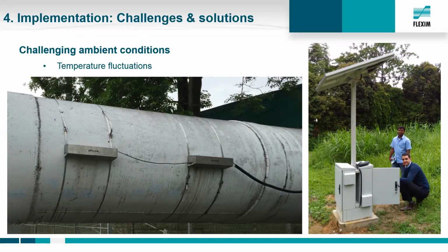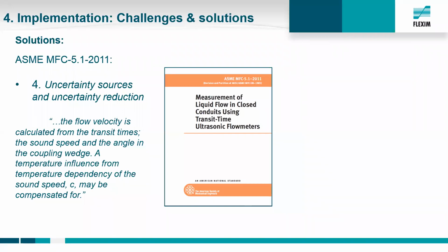Here we can see a nice installation from our Southeast Asian colleagues on a water main supply line, and these are totally exposed to the ambient environment. How this affects the measurement we will see on the next slide, because the ASME guideline already describes the effect and suggests temperature compensation. So what is the deal about it? The uncertainty of a measurement is affected by the sound speed of the liquid and the materials the ultrasonic pulse is traveling through. This is what I meant at the beginning. We have to keep it in mind for now.